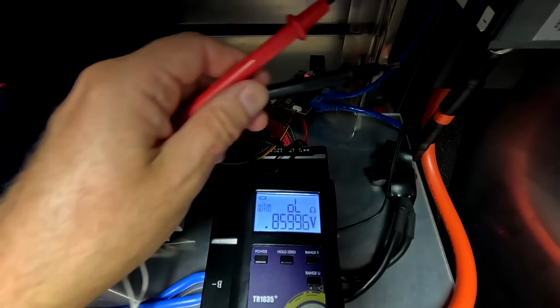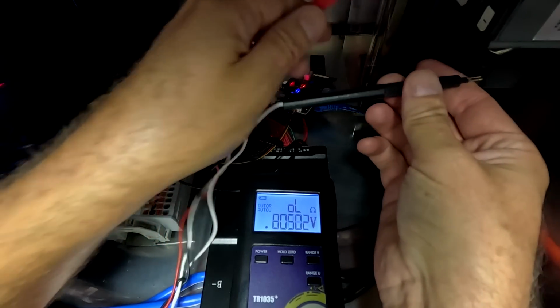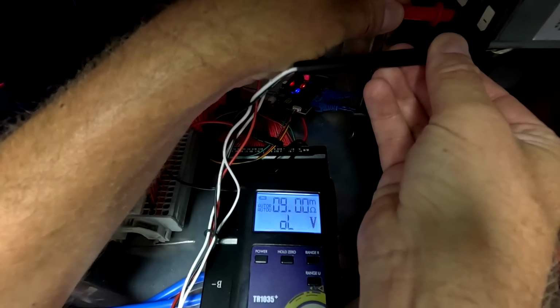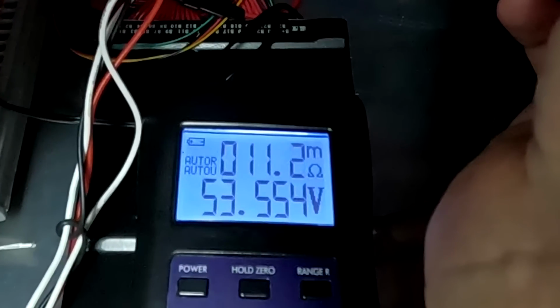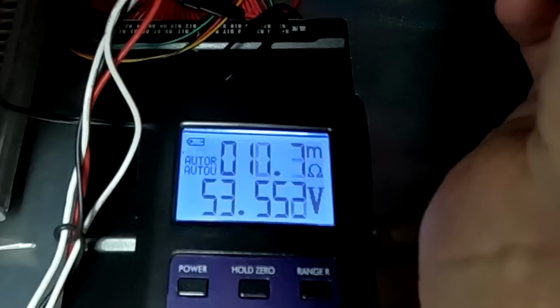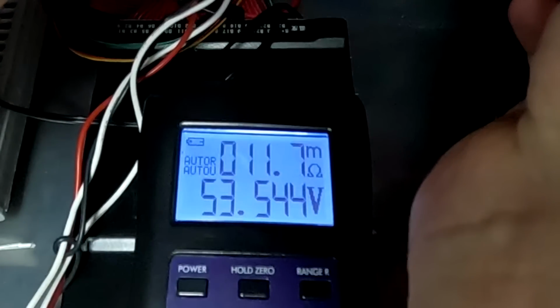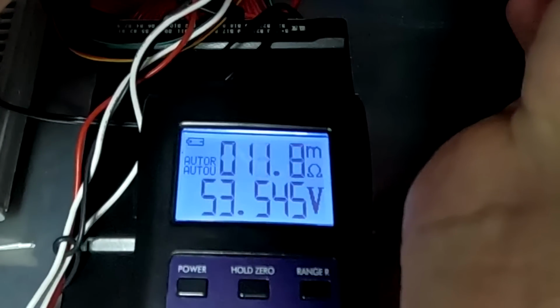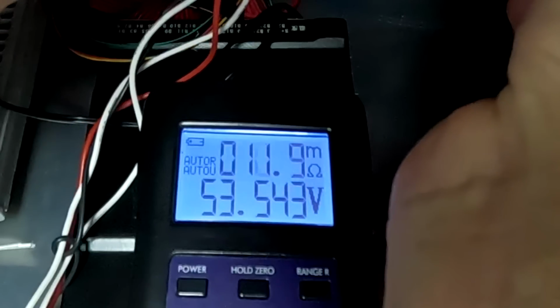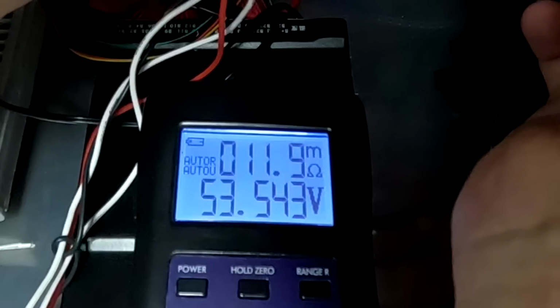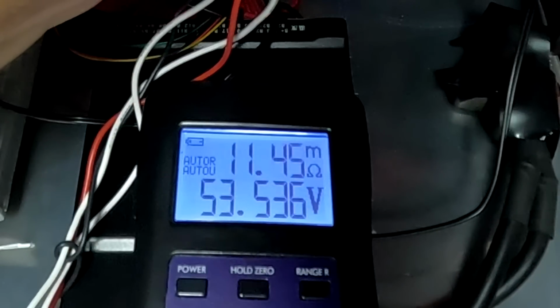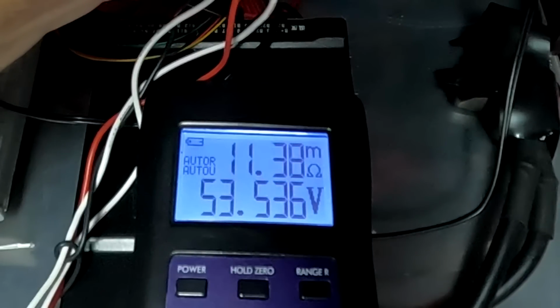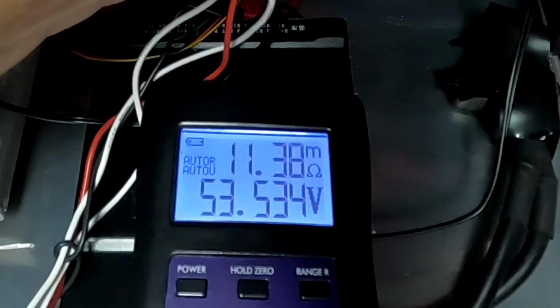So here the middle shelf battery is already turned off, isolated. Measure positive and negative here. We have 53.55 volts and an overall resistance of 11, 12, 13 - come on, be static - of 11.3 milliohms. 11.5, for, let's say, 11.4 milliohms.